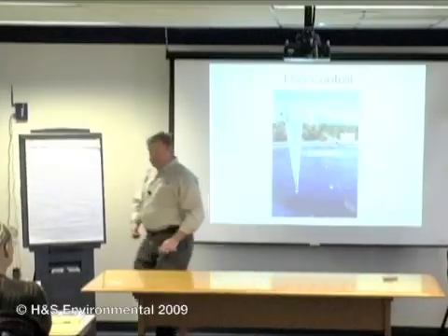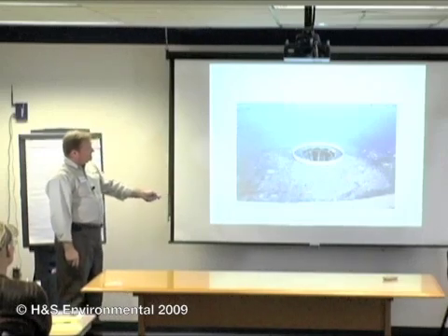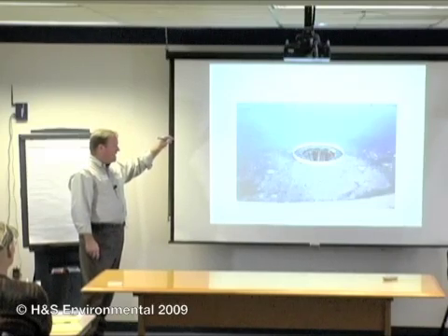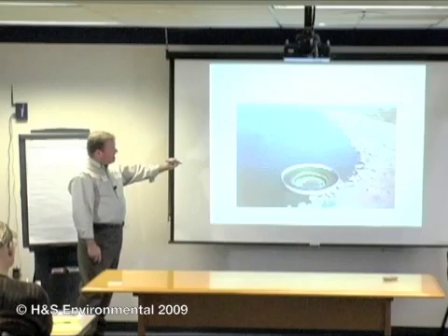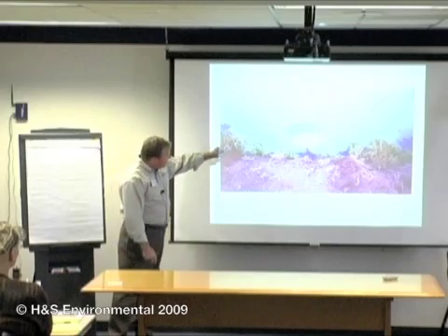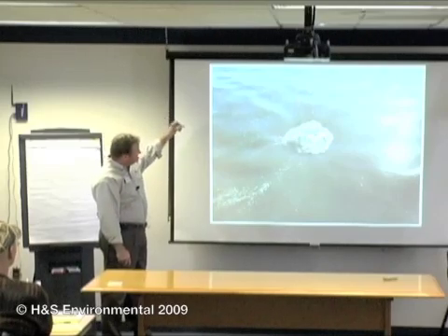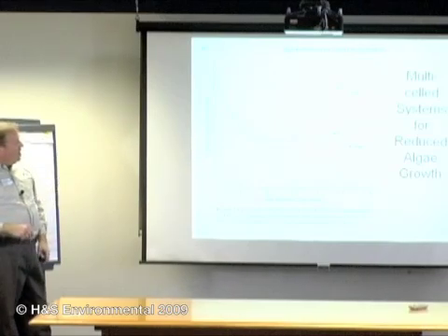Anything floating on top of the lagoon is potentially suspended solids — grease, trash, and similar material. Even with a baffle installed, garbage can still get through. Anything rising out of the sludge or floating on the surface can end up as effluent suspended solids. Algae concentrations and water quality change with increasing or decreasing depth. Controlling algae is also possible by influencing retention time through adding baffles or designing the lagoon system appropriately.